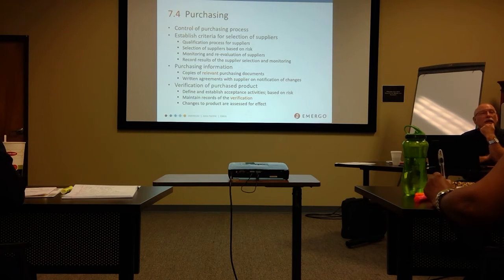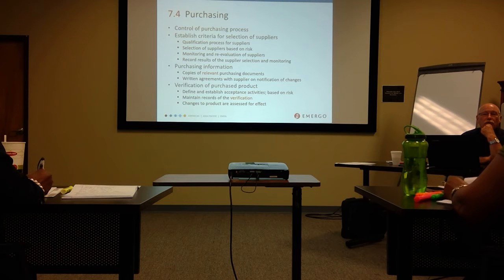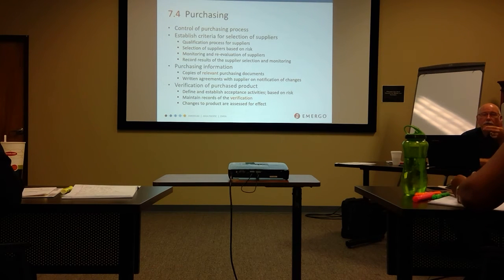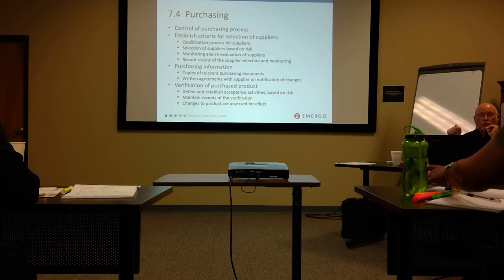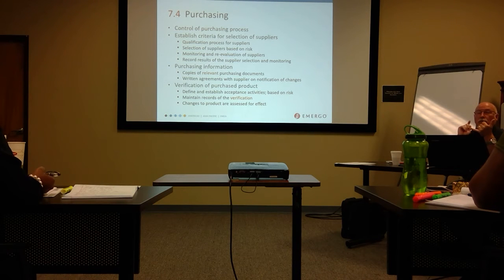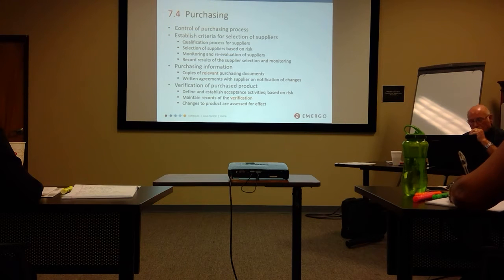So if as part of your incoming acceptance program it is important to take measurements of any type, make sure that stuff gets documented. That's a record — a quality record. It lives per your procedure on quality records. You cannot throw them away. That's a big deal — you'd be close to handcuff time if you do stuff like that. Somebody needs to make a determination on whether the material reviewed is acceptable — documented. The easy way to do this is on the form itself: here's what we received, here's what we sampled, here's what I inspected, here are the acceptance criteria, and somebody signs off to say 'approved for use' — traceable. We need to be able to determine who released it.